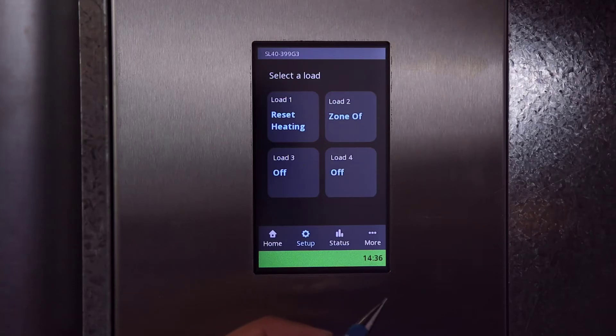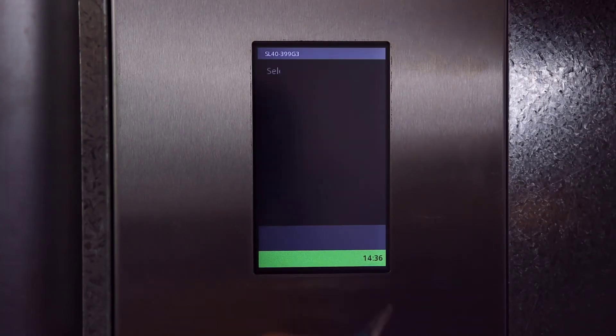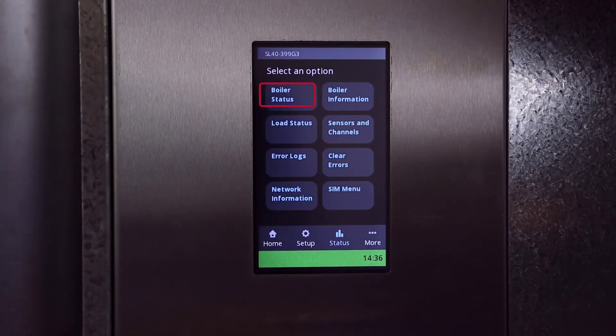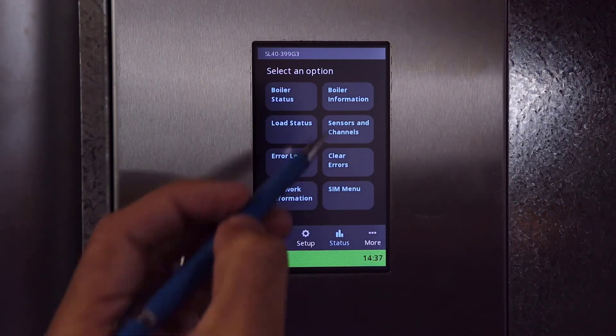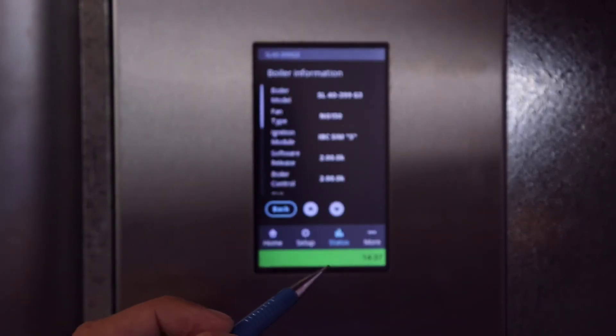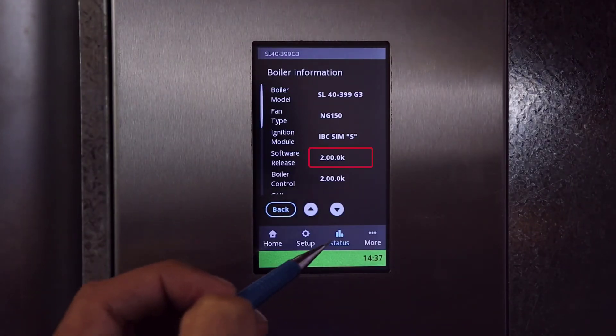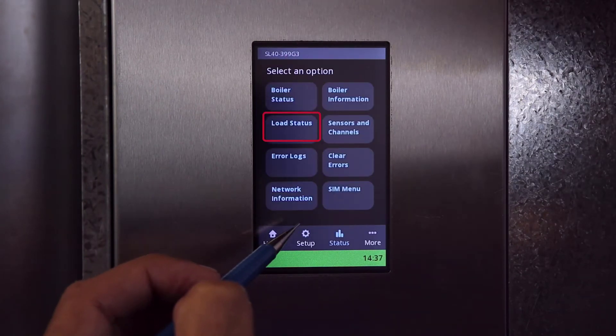Next is Status. Boiler status gathers into one menu all the sensor inputs, the heat input, and — except for older models — the flame current. Boiler information is where you'll find your boiler model and current version of software. Load status is where you can find runtime, priority, and other load details including load history graphs. Under sensors and channels you'll find the current values for all sensors attached to the boiler.